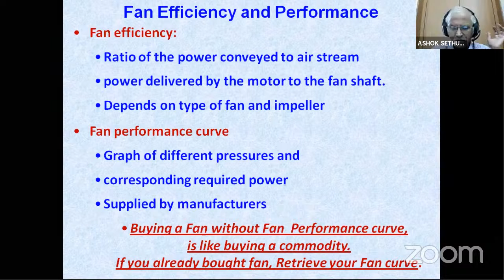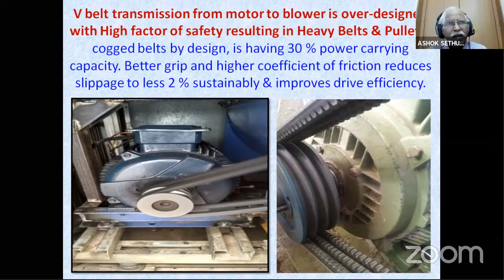Even on the blowers, the motor to machine power transmission by the belts also matters more. Previously, many industries went for strong belts. The motor may break or the blower may break, the belt will not break. But now they understood, they went for a cogged belt, and they are able to achieve energy savings. The slippage is also very much less, like a flat belt, and the V belt is getting outdated, obsolete now. These are all the motor to machine belt losses that are happening in the industry.